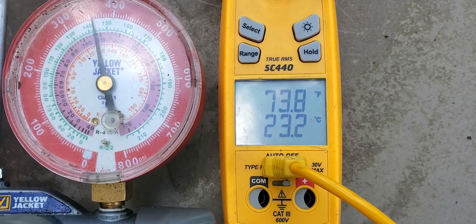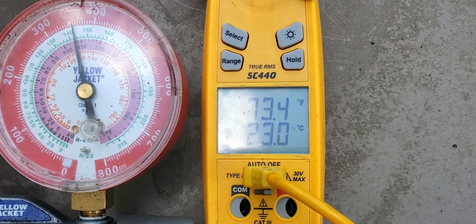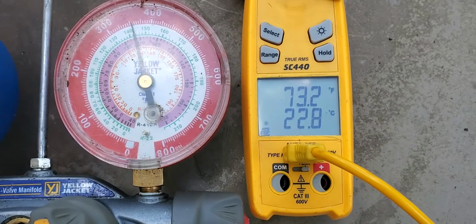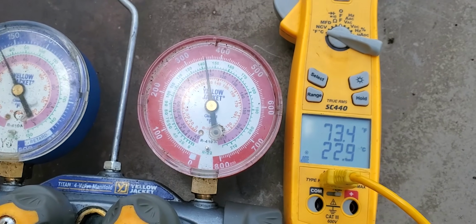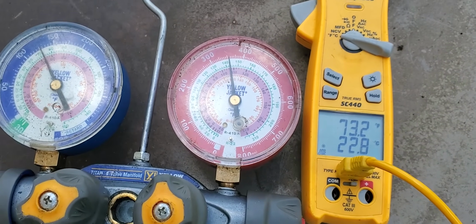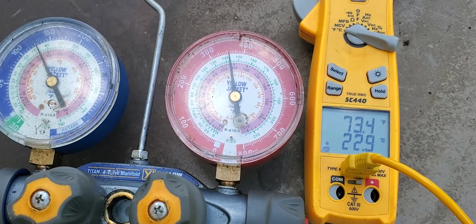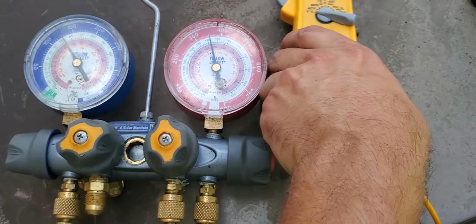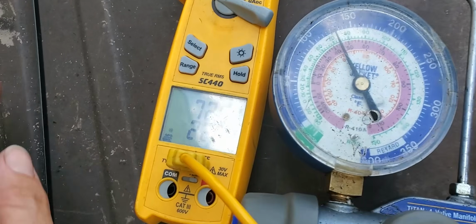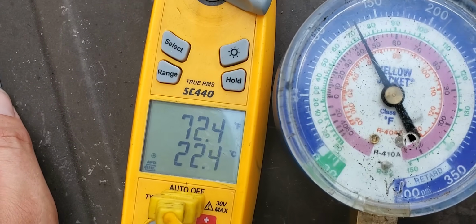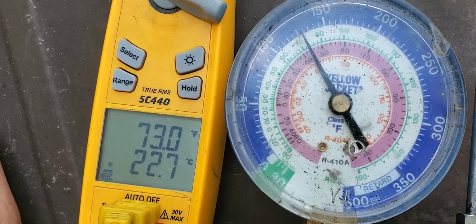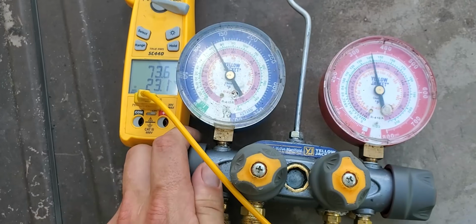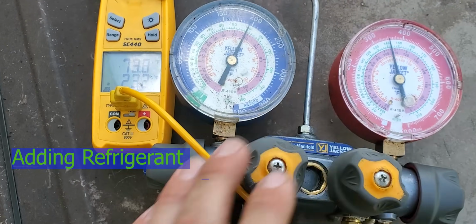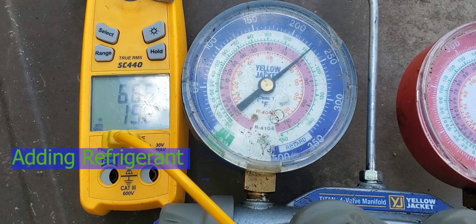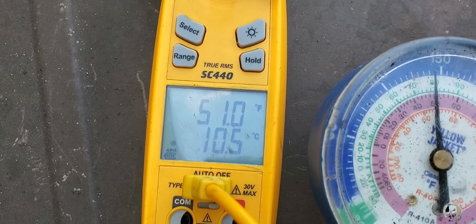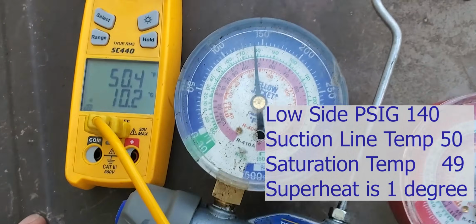A single package machine like this has a specific refrigerant charge that can be taken at face value. A split system, however, will have a refrigerant charge amount that is conditional on the distance between the condenser and the evaporator. You need to liquid charge with 410A because it's a zeotropic refrigerant. Initially, the refrigerant is liquid charged into the high side of the system. When the liquid line is filled to capacity, the remaining liquid is charged into the low side of the system.